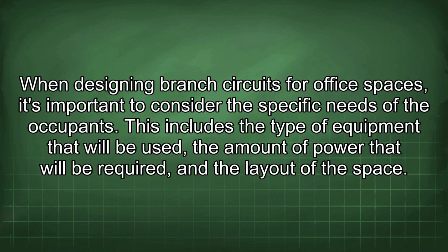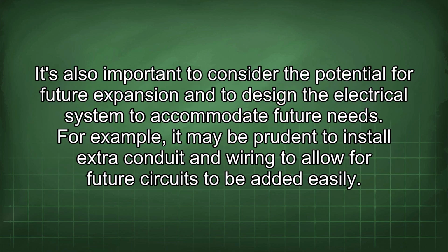When designing branch circuits for office spaces, it's important to consider the specific needs of the occupants. This includes the type of equipment that will be used, the amount of power that will be required, and the layout of the space. It's also important to consider the potential for future expansion and to design the electrical system to accommodate future needs. For example, it may be prudent to install extra conduit and wiring to allow for future circuits to be added easily.